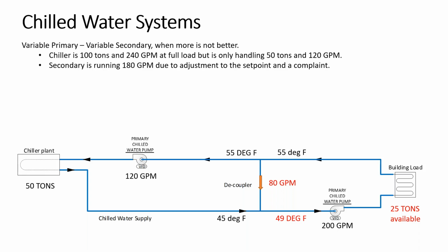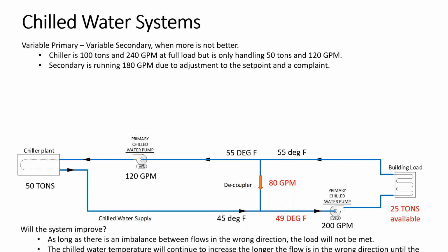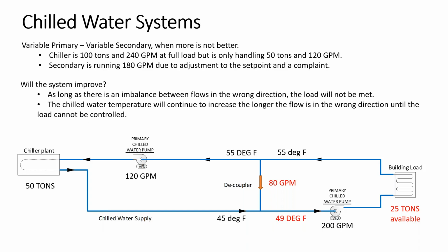Now it's a 55-degree return, you get a 45-degree supply, but now you've got 80 GPM going through the decoupler the wrong way. So now instead of 45-degree water like you've got coming out of the chiller, you've got 49-degree water going out to the load. You're actually reducing your tonnage available to the load, the more water you're pumping in that secondary. So this is, again, why you cannot overpump that secondary, because you'll mix the return water with the supply water going out to your load. You don't want to do that. You want to mix the supply water coming from the chiller with the return going back to the chiller to unload the chiller. Chiller hasn't changed a bit, but your load is increasing out there on the system, but you don't have enough cooling capacity to cool the building.